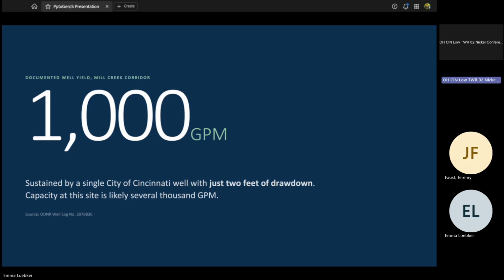That particular well only experienced 2 feet of water level drawdown. So if the static water level is, say, 20 feet below ground surface naturally, when you turn the pump on it goes down 2 feet. Pretty good — that tells me you can actually pump it a lot harder, because you have a lot of available drawdown in your well. For the engineers in the audience, maybe you could pump it at 5,000 gallons a minute, which corresponds to a pretty significant heating and cooling load.